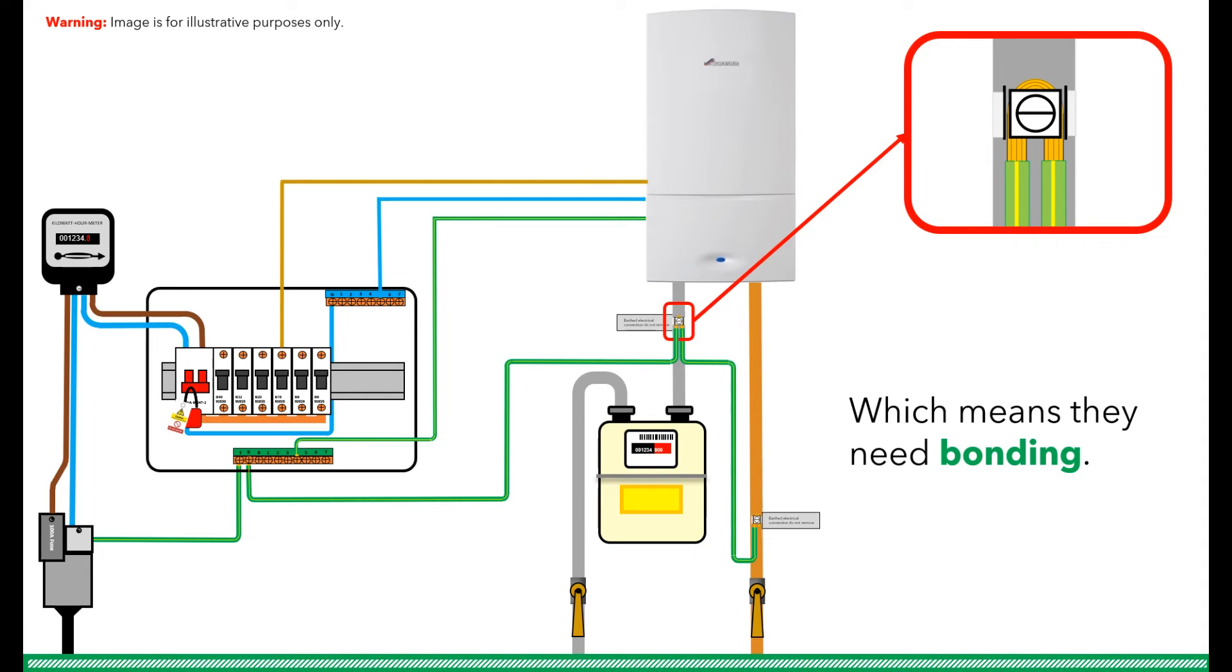This means that there is another extraneous conductive part that needs bonding too. And if you use the same cable for both, remember that it needs to be uncut or unbroken, so that if the first clamp comes off or is loose, the second clamp is still effective and sufficient. As you may have noticed by now, other trades have a habit of removing the first clamp when altering pipe work and not reinstating the clamp afterwards, which means the bond to both pipes could be simultaneously lost.